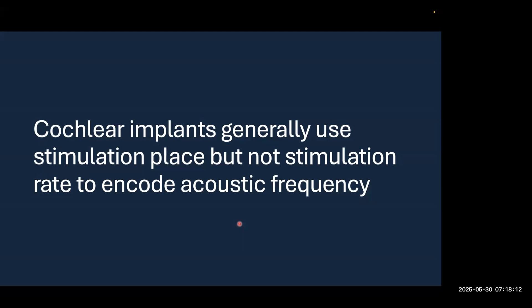Okay, so with that, how do cochlear implants typically stimulate? What is the most common way of stimulating? So the most common way for cochlear implants to work, the most common signal processing, is that sound comes in and is broken into a bank of bandpass filters, so kind of emulating the basic function of the cochlea. And so it's broken up into high frequencies down to low frequency processing channels. The output of that, the temporal envelope, is extracted. And this is the part where the faster timing information, which we refer to as the temporal fine structure, the fine timing information, is discarded. And there's historical reasons why this algorithm was developed, and I can kind of go into that. But the key point is this is where it's discarded.